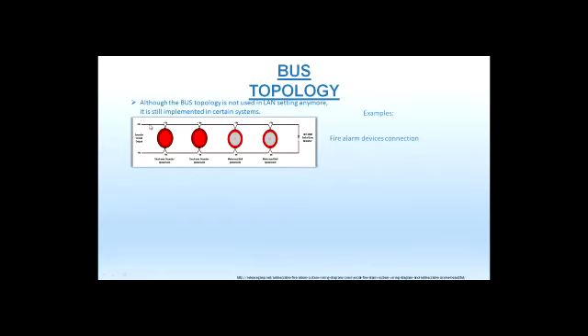In the fire alarm, all the devices are normally open, and there's something called an end of line resistor. The zone looks for that resistor, and if it sees it, it thinks everything is okay. If one of the devices triggers, it shorts that out, so instead of seeing the resistance of the end of line resistor, it sees a dead short. That means something has triggered.